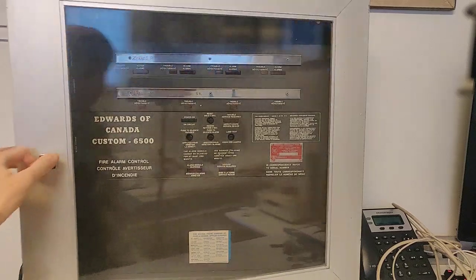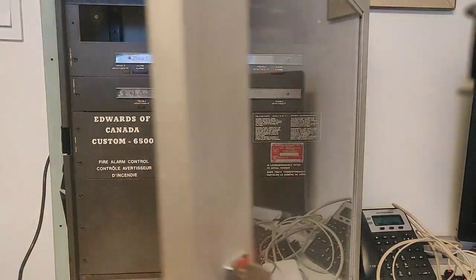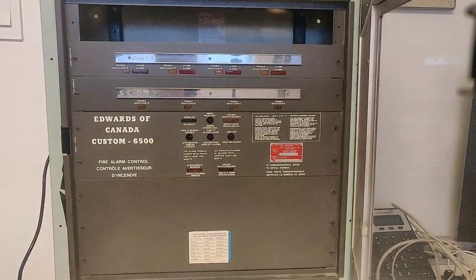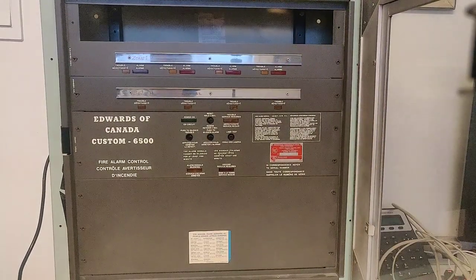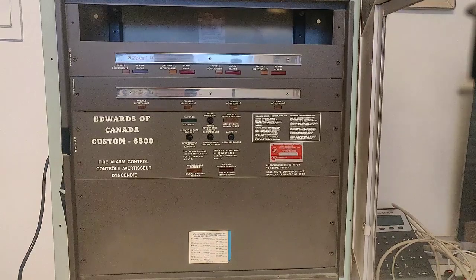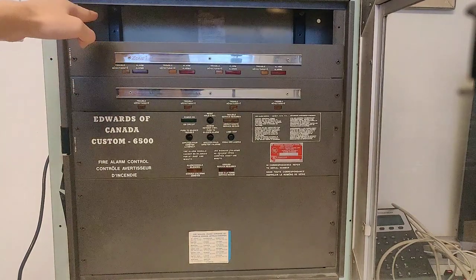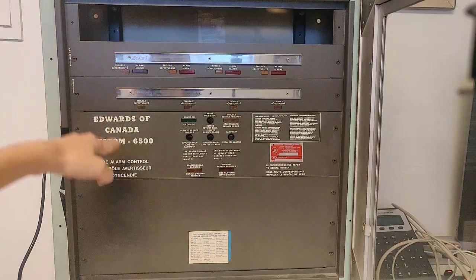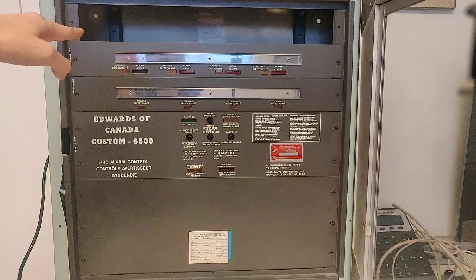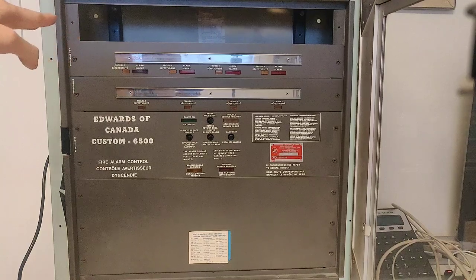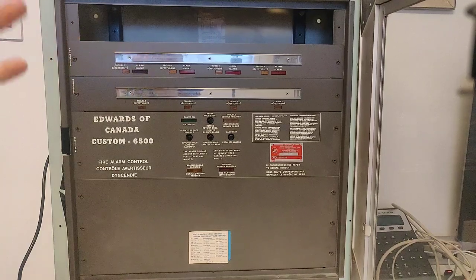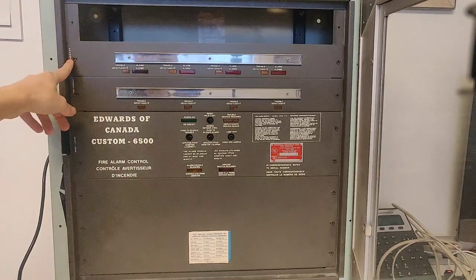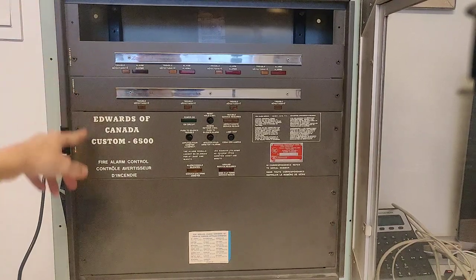Opening the door up, we can reveal the internals, the dead front. One of these panels is missing. That's one of the most common issues you'll find with these panels—you breathe the wrong way or look at them the wrong way and they'll fall right out. They're held in with these little spring clips, but they kind of suck.